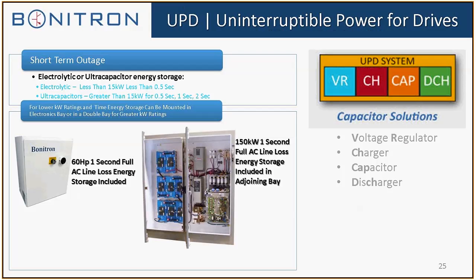Here's some short-term or capacitor solution configurations. Over in the bottom diagrams, the left is a 60 horsepower 1 second full AC line loss. This is a wall mount cabinet, and it can have a display, or it doesn't have to have a display. But once again, I recommend that display. So the energy storage can be put inside with the electronics in a lot of cases if you're right around 60 horsepower or below. When you get up into the higher kilowatts, you have to look at two cabinets.